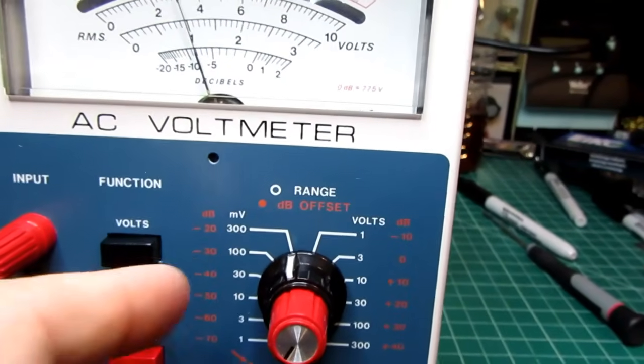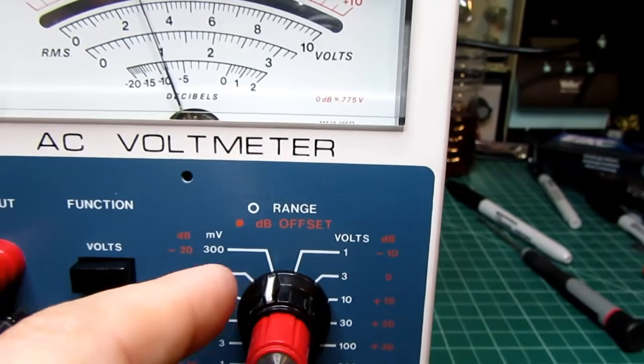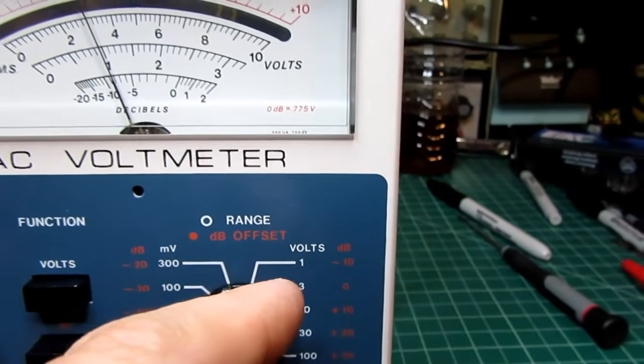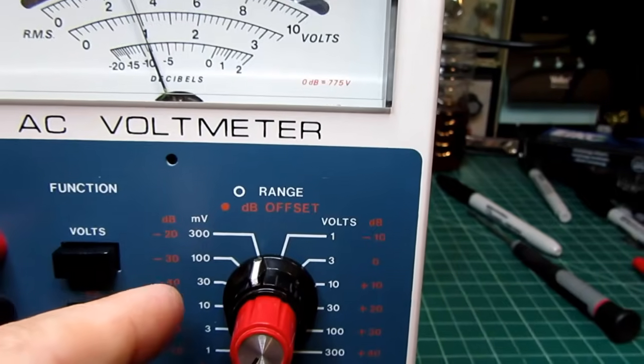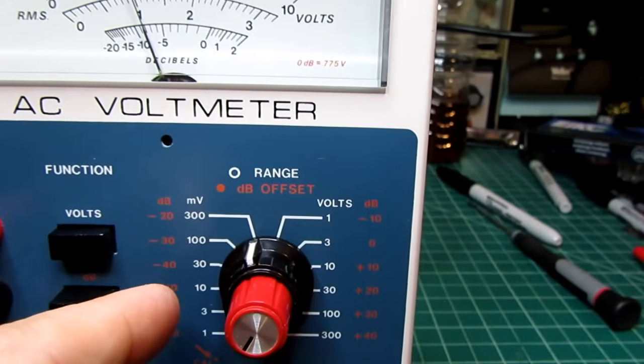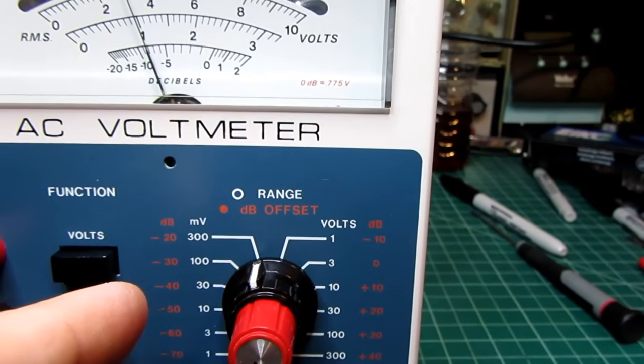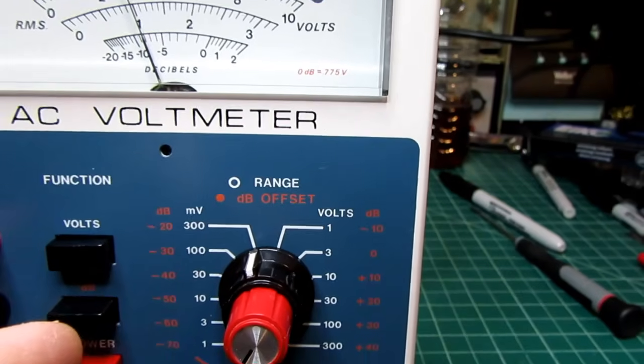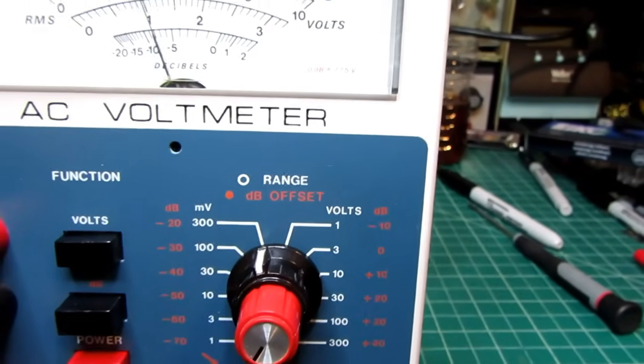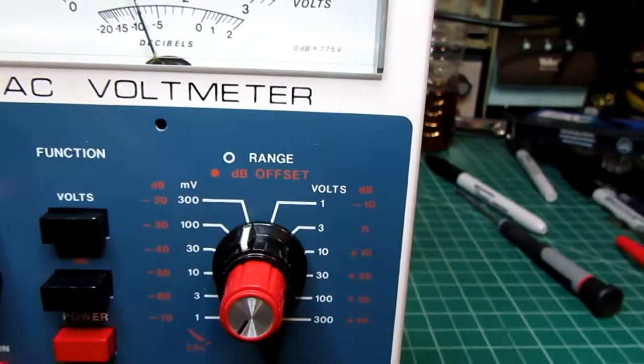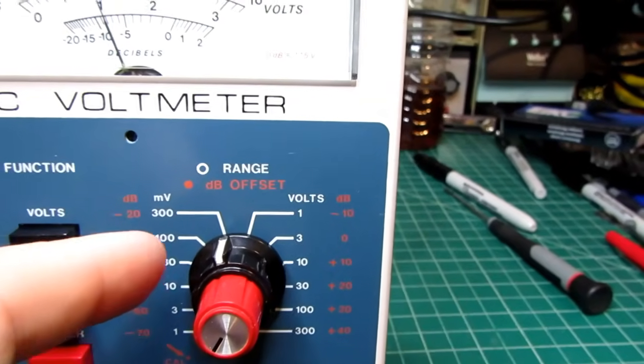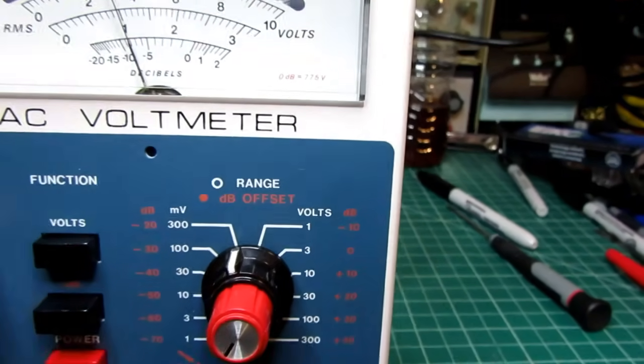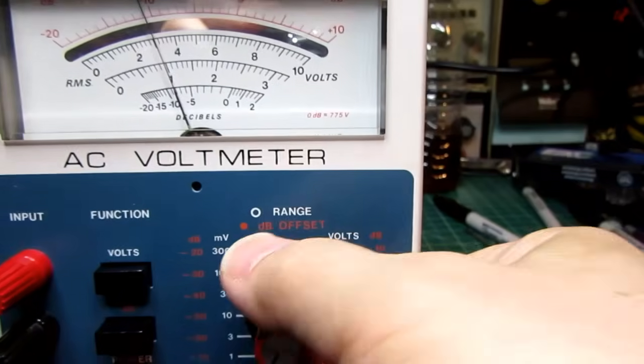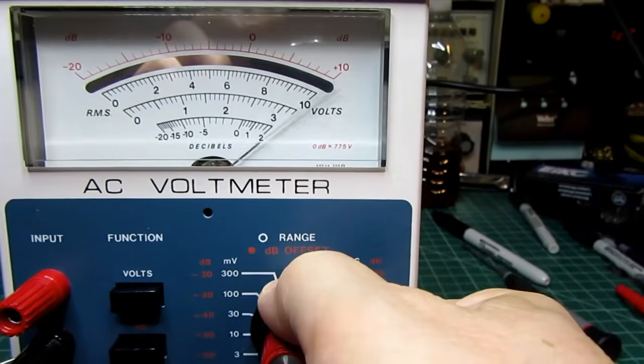The only other difference between the 3 scale and the 1 scale, or the 300 millivolt and the 1 volt, any of the other scales starting with 3 or the ones starting with a 1, are different only in the sense of the attenuation resistors, and they have nothing to do with calibration. So if I get reasonable readings on both of those, then there's nothing more I can do.